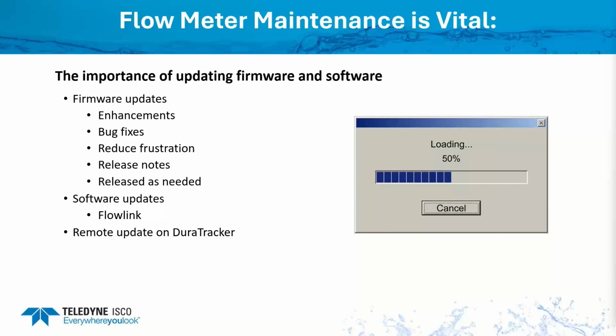Now, one thing with our DuraTracker, that actually has the ability for remote updates. So instead of going out to the site, if you have a modem on there, you can push the update to the instrument and let it update in the field while you're sitting in the office.